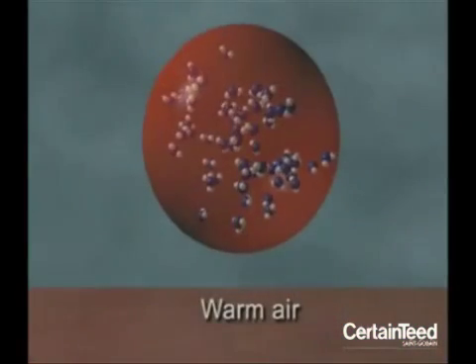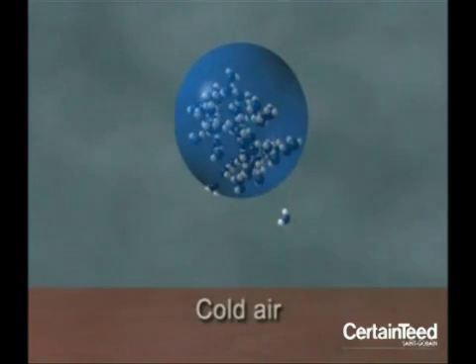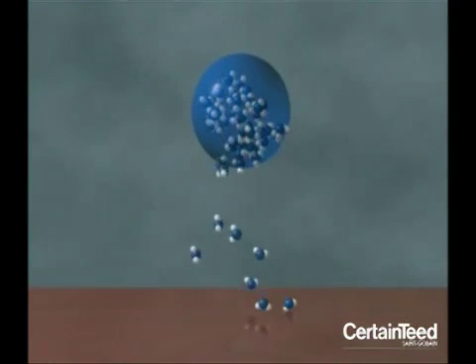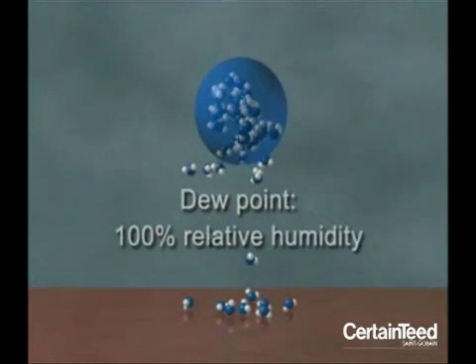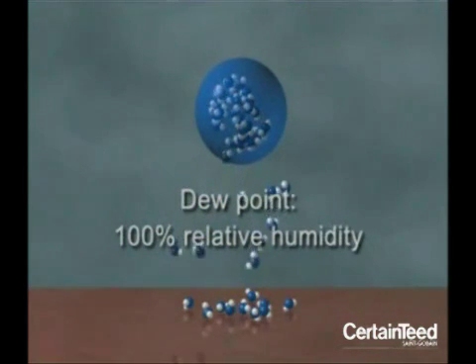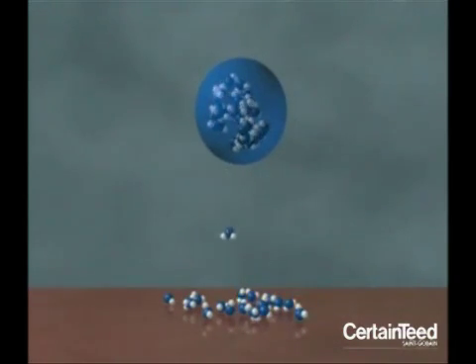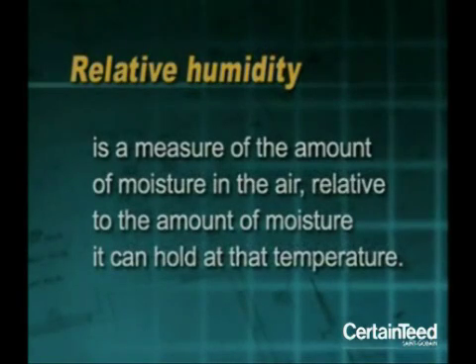We know warm air can hold more moisture than cold air. The temperature at which the moisture starts to condense is called the dew point. At the dew point, the air is completely saturated with moisture and can't hold anymore, so we call the dew point 100% relative humidity. We think of relative humidity as a measure of the amount of moisture in the air relative to the amount of moisture it can hold at that temperature.